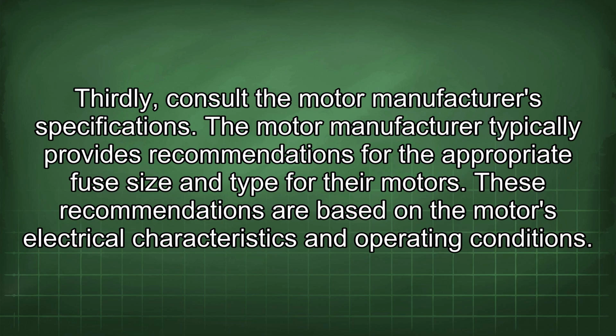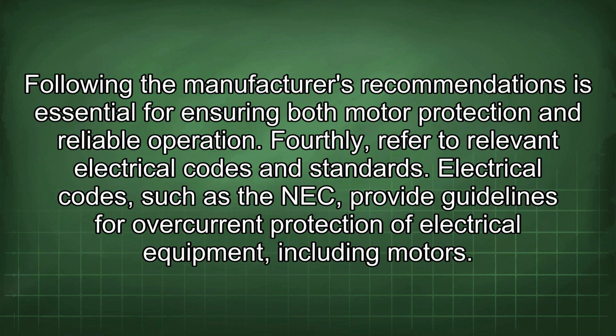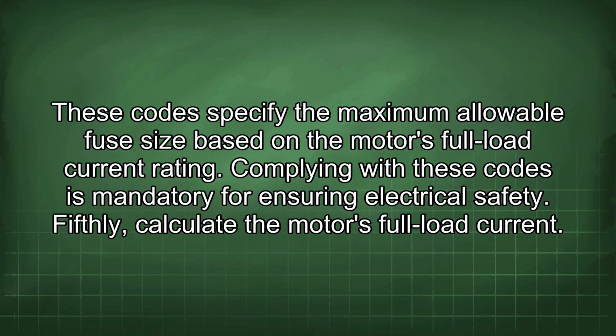The motor manufacturer typically provides recommendations for the appropriate fuse size and type for their motors. These recommendations are based on the motor's electrical characteristics and operating conditions. Following the manufacturer's recommendations is essential for ensuring both motor protection and reliable operation. Fourthly, refer to relevant electrical codes and standards. Electrical codes, such as the NEC, provide guidelines for overcurrent protection of electrical equipment, including motors. These codes specify the maximum allowable fuse size based on the motor's full load current rating.